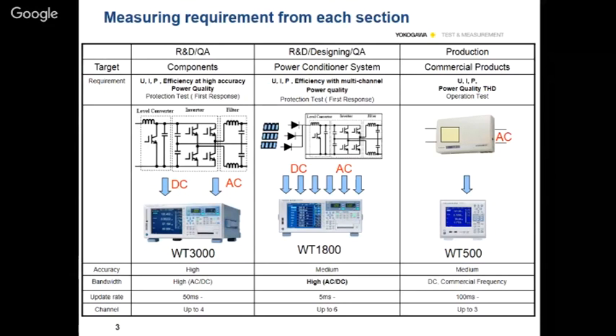So it will calculate with high accuracy, bandwidth, and update rate of 50 milliseconds. Normally other power analyzers have a 1 second or 500 milliseconds update rate for data capture. If you want to capture a fast response, like a transient waveform, even with a very good power analyzer, if you're not able to capture data with a lesser interval, you won't be able to see the transient or the spike. So the update rate also plays an important role in terms of acquiring data correctly. That is the application.